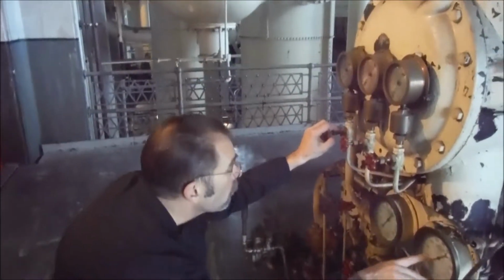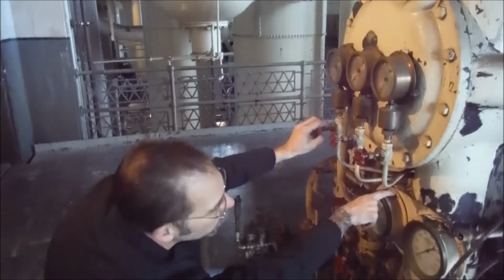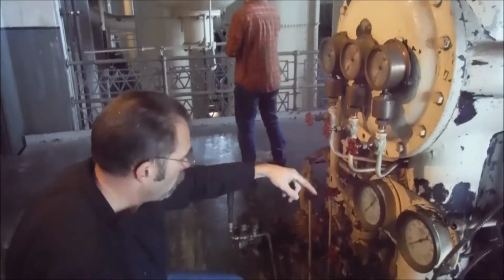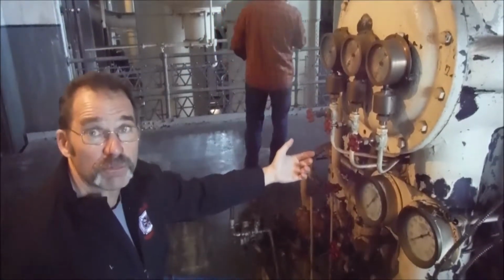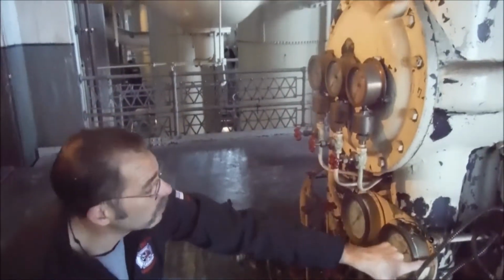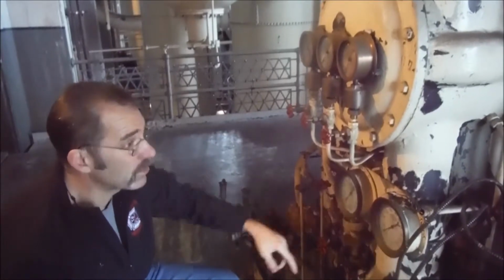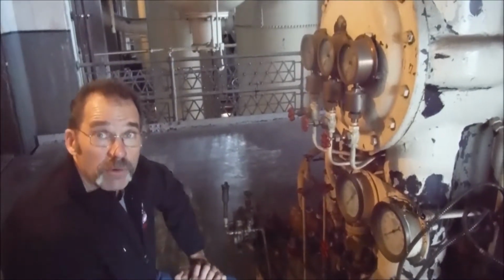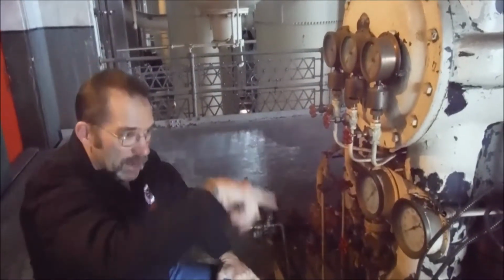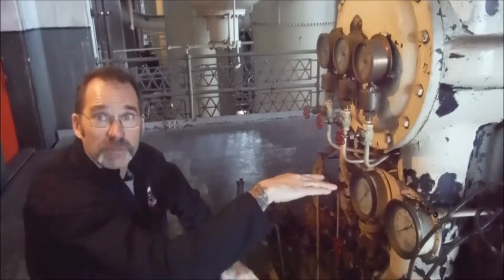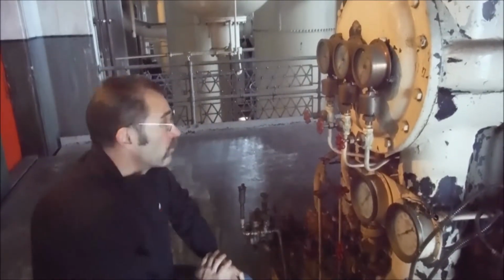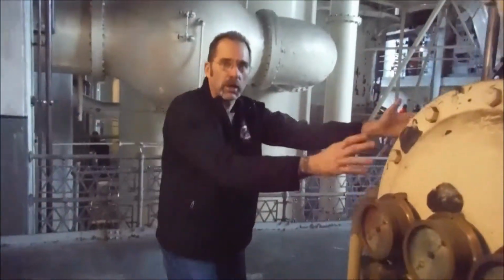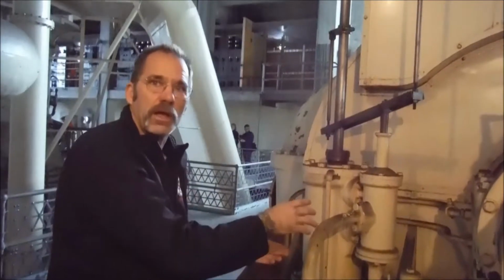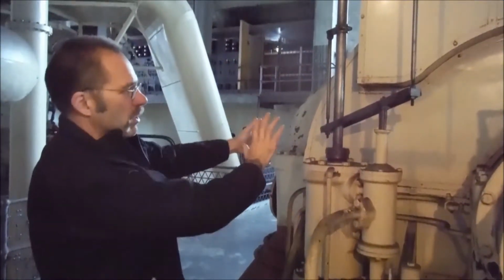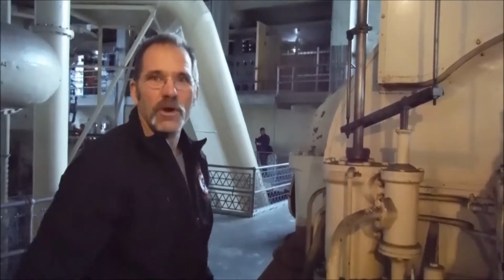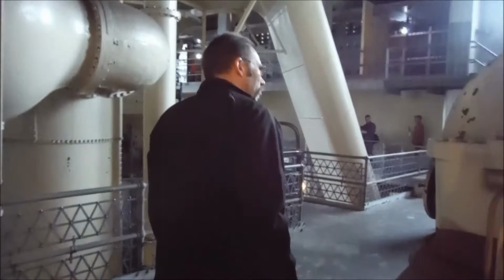Mercury steel tube thermometer. And this is labeled oil cooler, and this is labeled thrust. So the oil system on here obviously has a heat exchanger to keep the oil from being too hot, so that'd be the oil cooler. And since somebody wrote thrust on here, I'm 90% sure that's the temperature of the thrust bearing. That would make sense. The steam hits one side of the turbine and makes the turbine spin, but the steam's coming at the turbine from the side, so it does generate axial thrust. So there's thrust bearings either in here or on the back side of the turbine, between the turbine and the generator, because that turbine wheel can't move more than a couple thousandths this way and that way without horrible things happening. Rampant badness may ensue. Yeah, horrible things.